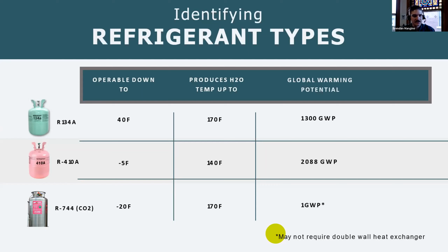Another thing to note is that this has a GWP of 1 because you're comparing CO2 to itself. One thing to note with these is that with the current pieces of technology, you can't do a split system because they have a high operational pressure of, I think it's 1400 PSI, which is just way too high for modern split system line sets.